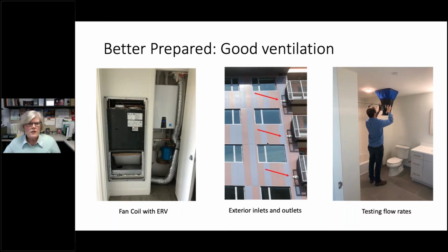So ventilation needs to be addressed at the unit level, and we have to make sure it functions well. The picture on the left is a fan coil unit with an ERV built into it, an energy recovery ventilator, so that you have constant background air with direct supply to the unit, but then trying to reduce the energy penalty of ventilation by having that energy recovery element in the ventilation system.